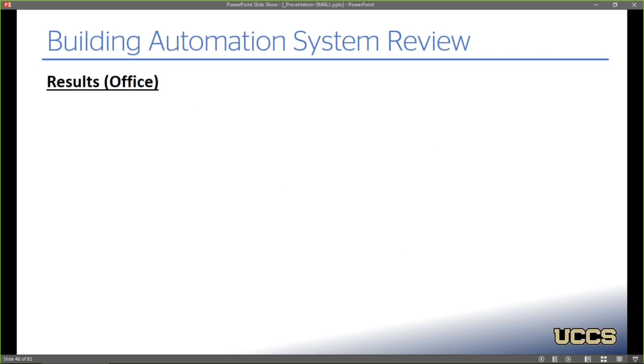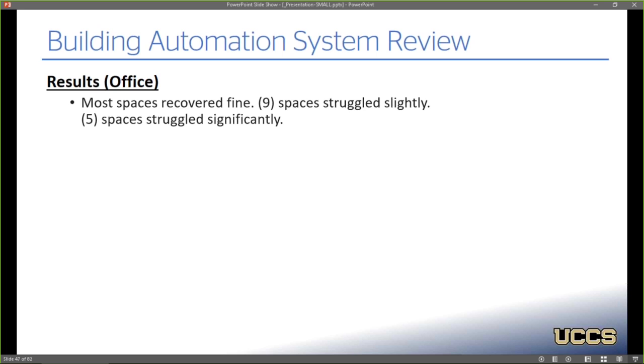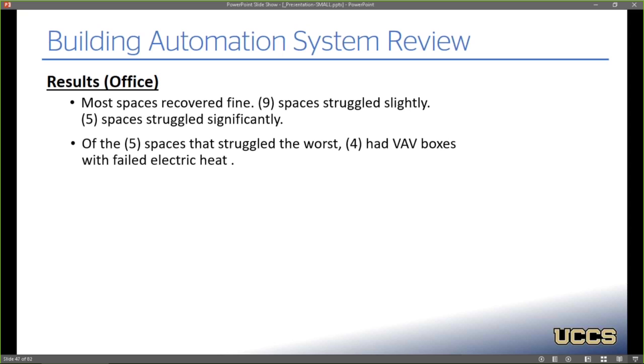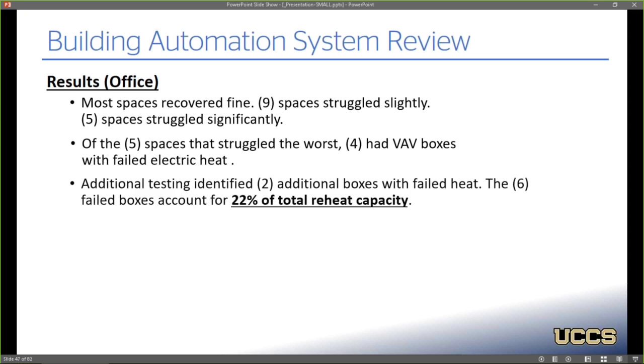So the results of that test, at the office, most of the spaces actually recovered pretty well. 9 spaces struggled a little bit, and 5 spaces struggled significantly. Taking a closer look at those 5 spaces, 4 of them appeared to have failed electric heat at the VAV boxes. So I went through and tested every other box in the building and found 2 additional boxes with failed heat. So with those 6, that accounts for about 22% of the total reheat capacity at that building.